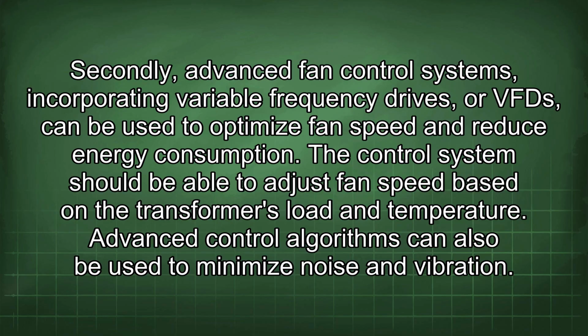Secondly, advanced fan control systems incorporating variable frequency drives, or VFDs, can be used to optimize fan speed and reduce energy consumption. The control system should be able to adjust fan speed based on the transformer's load and temperature. Advanced control algorithms can also be used to minimize noise and vibration.